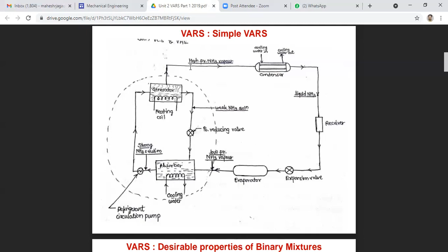Next point, we are going to discuss the desirable properties of binary mixtures. First, it has a great affinity to absorb the refrigerant used. Second, low surface tension to facilitate absorption of the refrigerant. Third, it should remain liquid throughout its cycle. Next, low vapor pressure at generator temperature and stable at the highest temperature of the cycle. Fifth is low specific heat and low viscosity for better heat transfer and minimum pump work. Next, a suitable pressure temperature relationship to meet the practical conditions needed in various components of the system. These are some of the desirable properties.